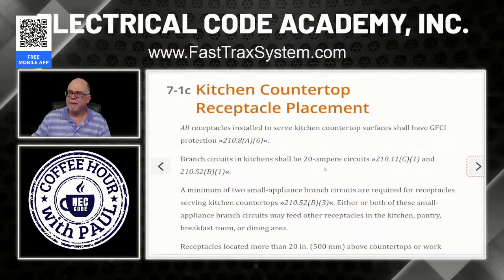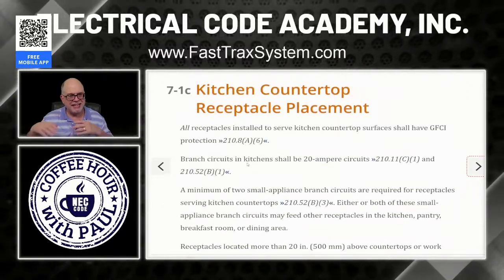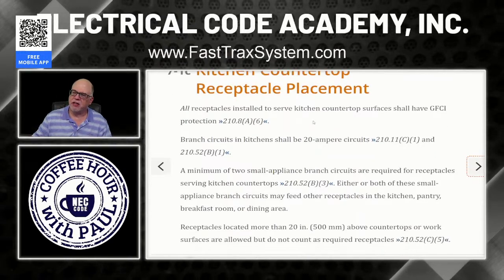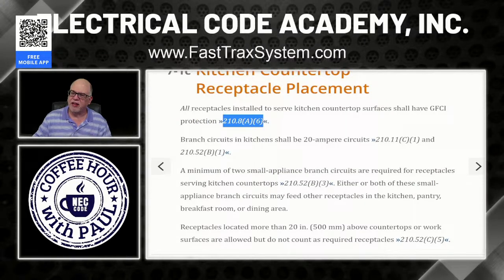All right? So we talked about the countertop spacing, and so we're going to look at it even more. We're getting even deeper with this episode. So we kind of touched on it, but now we're going to put all of that we learned into practice. Ready? All right, kitchen countertop placement. All receptacles installed to serve the kitchen countertop surface shall be GFCI protected. That is 210.8(A)(6). Remember, go look that up.